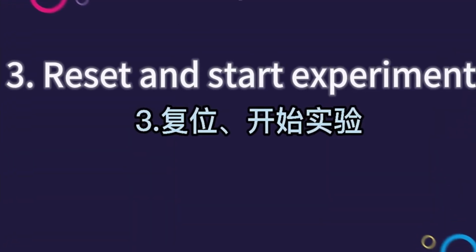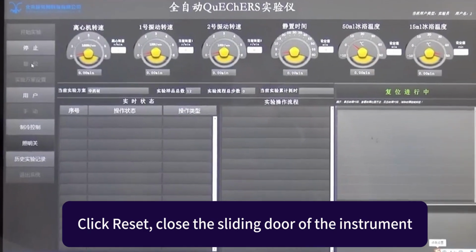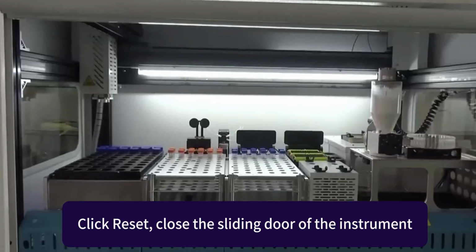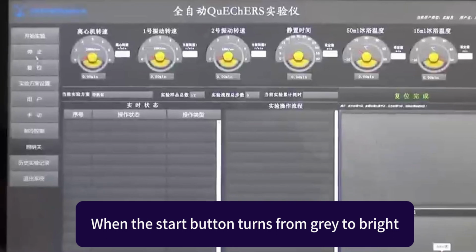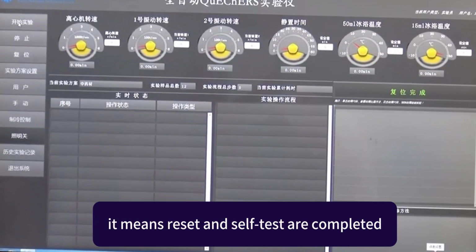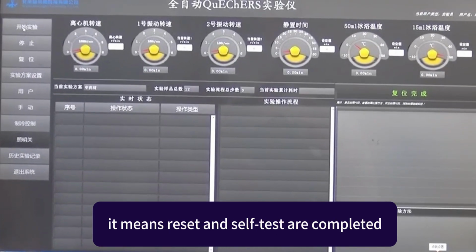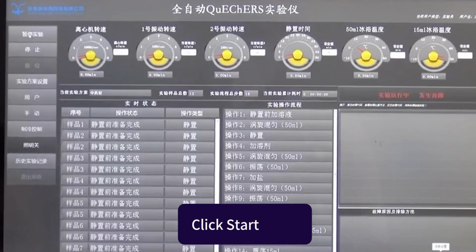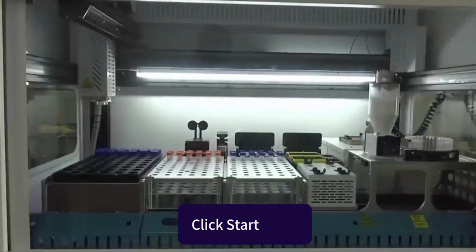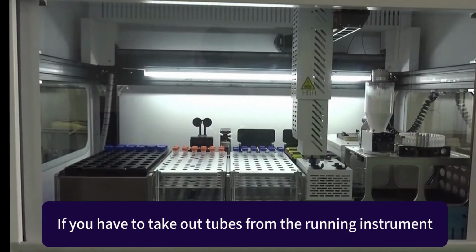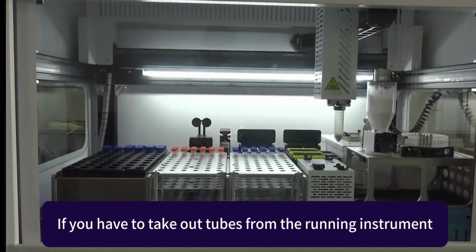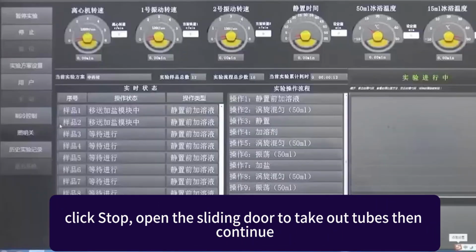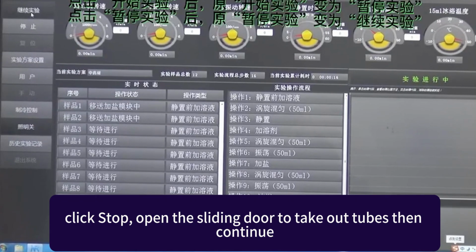Three. Reset and start the experiment. Click Reset. Close the sliding door of the instrument. When the Start button turns from gray to bright, it means reset and self-test are completed. Click Start. If you have to take out tubes from the running instrument, click Stop. Open the sliding door to take out tubes, then continue.